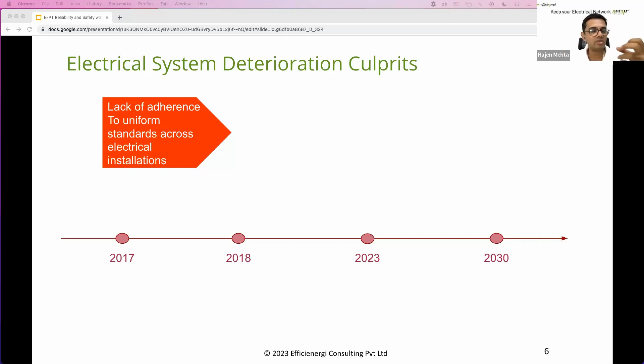Second are some factors that are happening. We are adding 500,000 AC drives annually, which are non-linear loads, and that's going to cause the system to deteriorate to a certain extent, in terms of power quality, harmonic pollution, and the high frequency switching devices getting added to the system. There are 26 cities with metro projects already, with 35 more cities proposed. Metros are again non-linear loads at the end of the day, and will add a burden on the grid. There's also a mix of traditional and modern loads inside facilities, another reason: you have traditional inductive loads within the facility, alongside non-linear loads sitting inside the same facility.